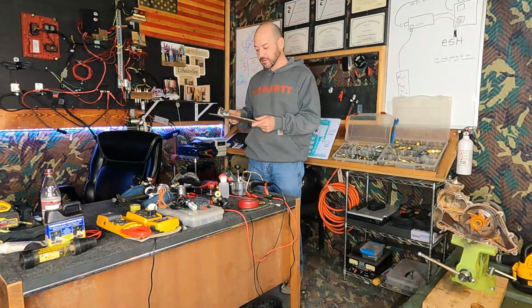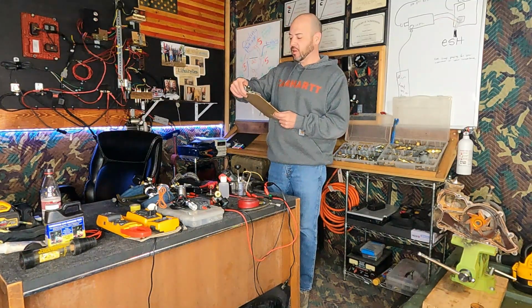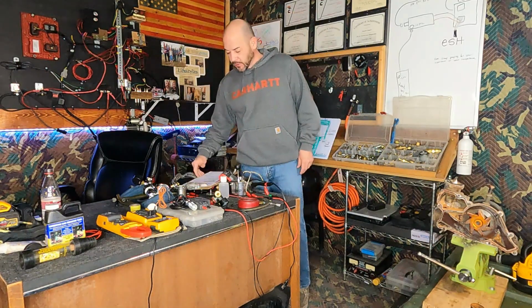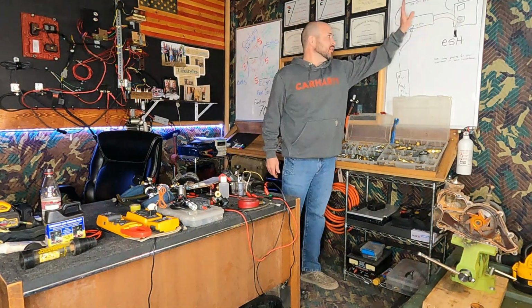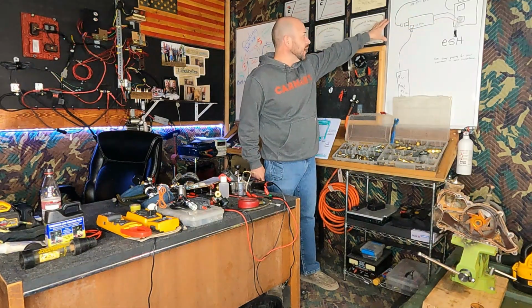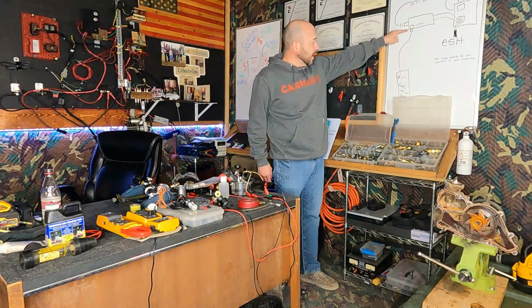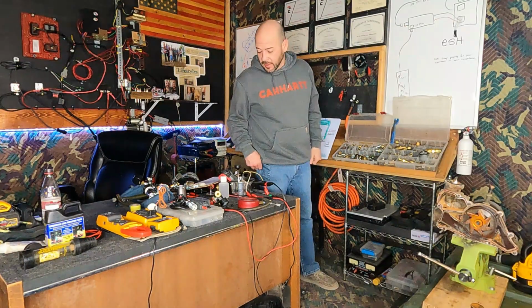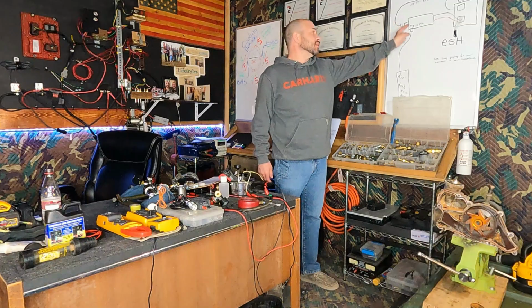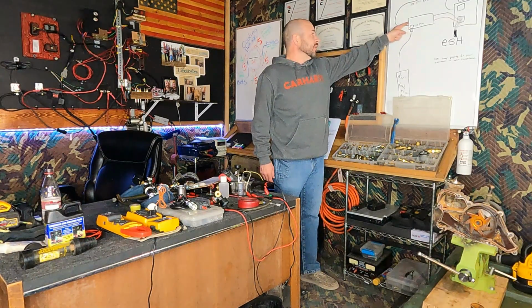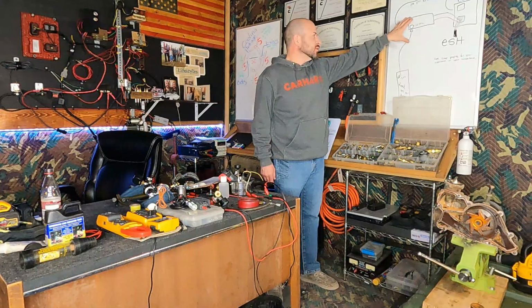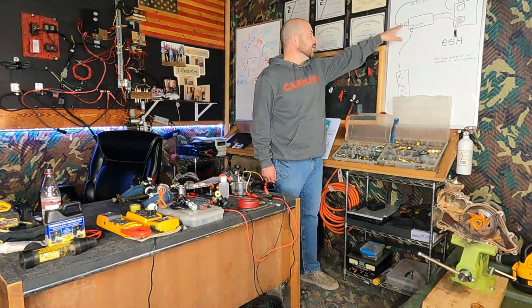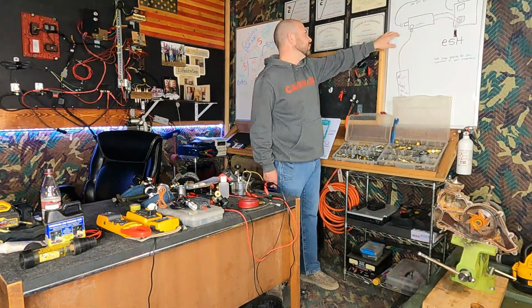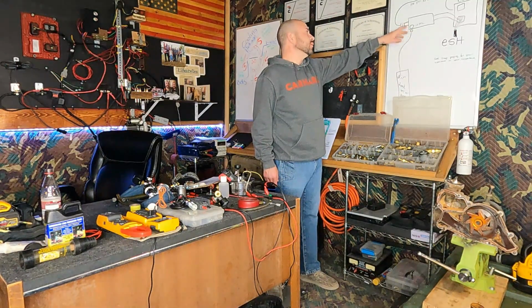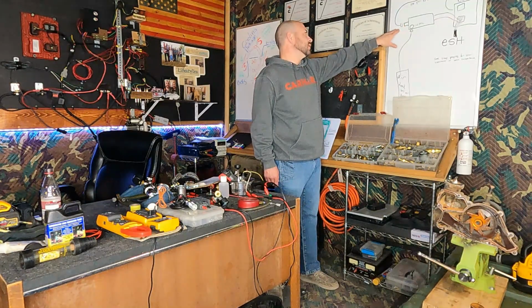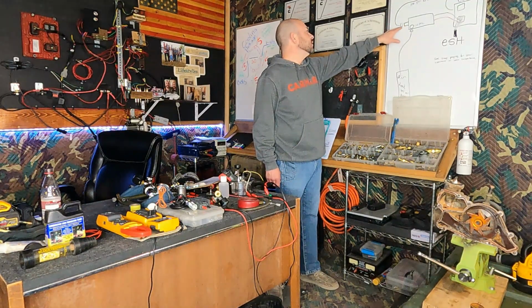Got a backside too. When we talk about the fans, I'm going to separate the problem. These fans operate with the ECM controlling one side, and the other side is controlled by air. So I have to make sure I have the applied air that I need to the solenoid, right? And I need to make sure that when I operate the solenoid—some of them are normally closed, some are normally open. They're all wired different, but air pressure releases. So a normally closed one and a normally open one will operate in reverse of each other. Know what it is you're working on—Cat, Detroit, they all seem to find their own way about it.